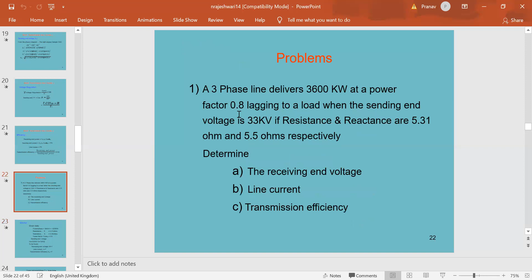So the given data: power per phase is 3600 kilowatts divided by 3, because it's a three-phase power. So 1200 kilowatts is the power per phase, the resistance is 5.31 ohms, and the reactance is 5.5 ohms. The power factor cos phi r is equal to 0.8 lagging.